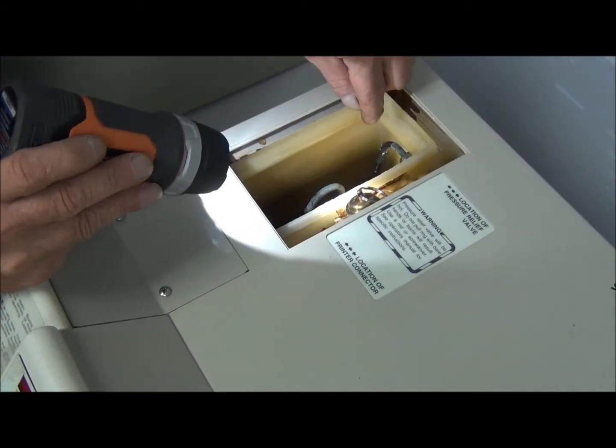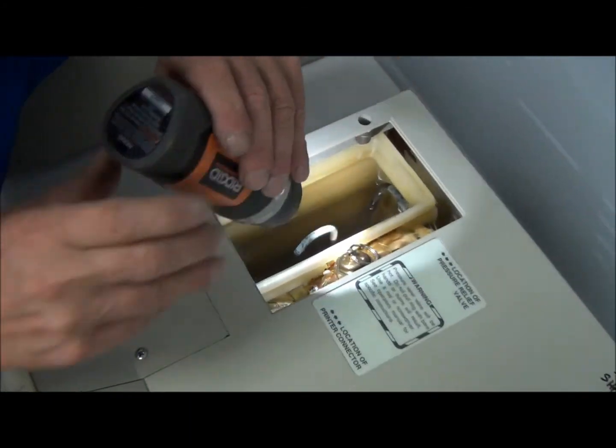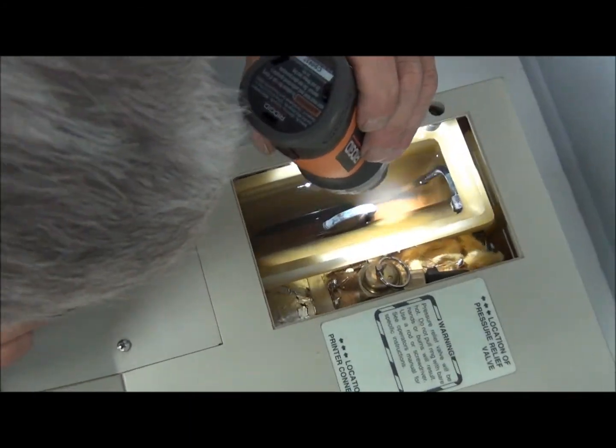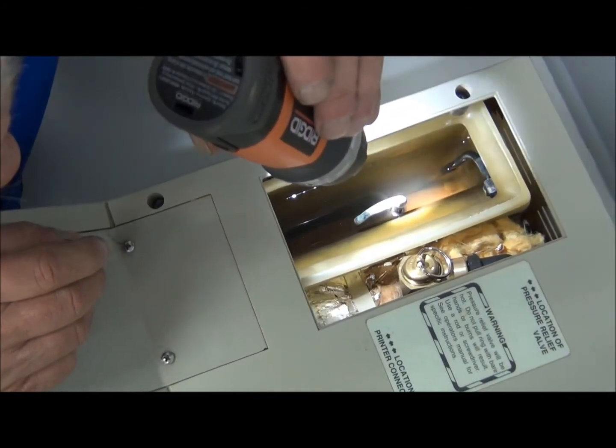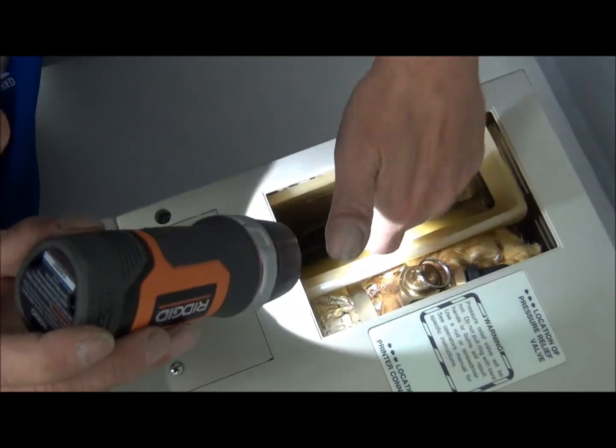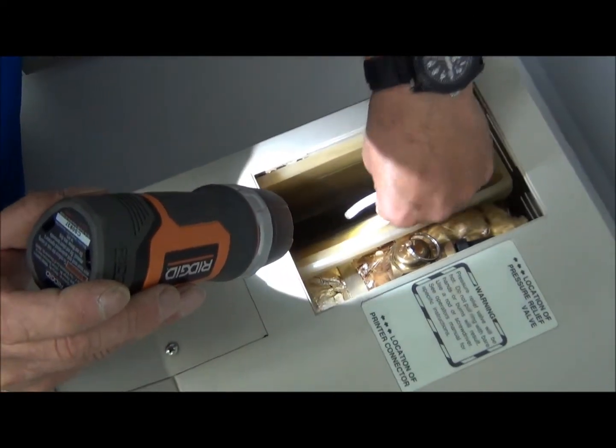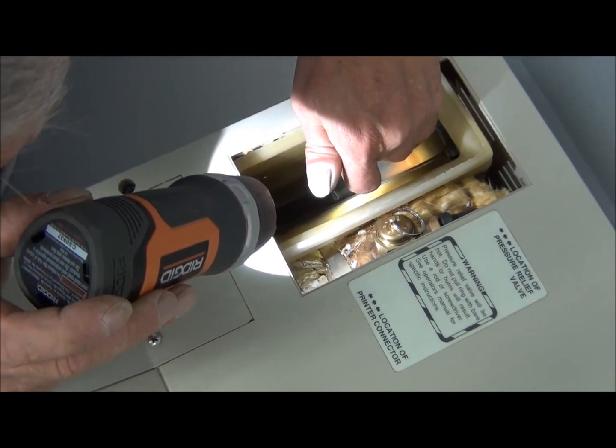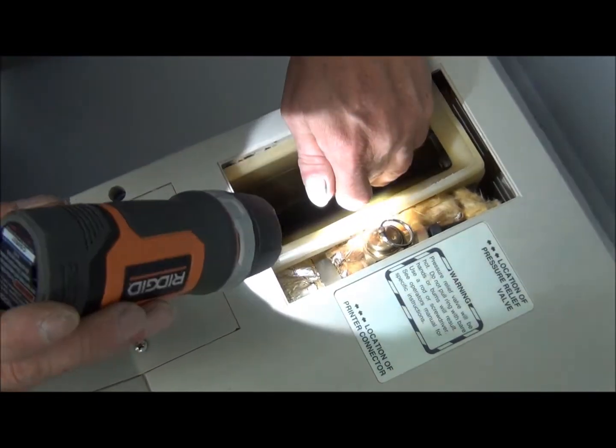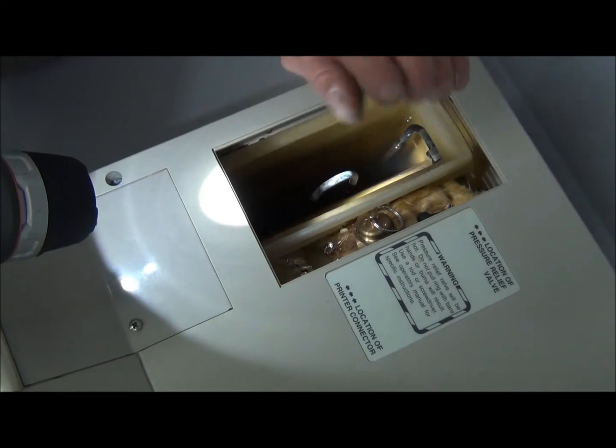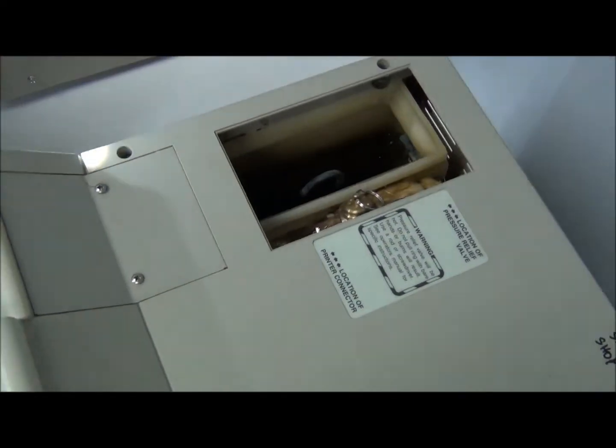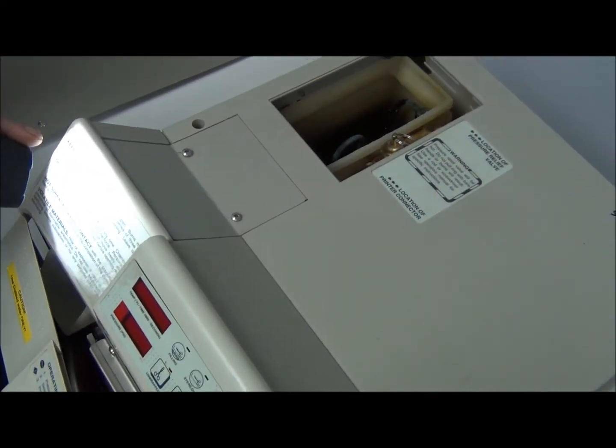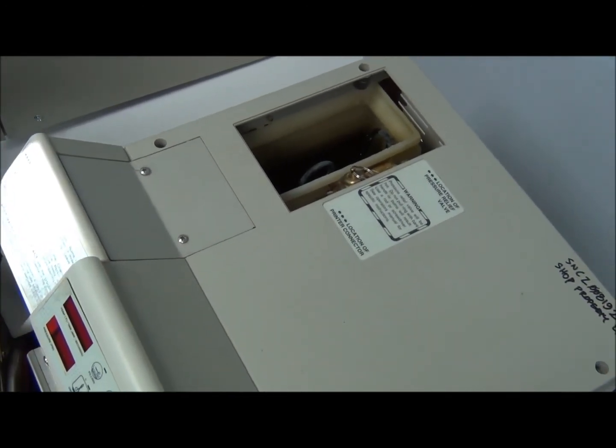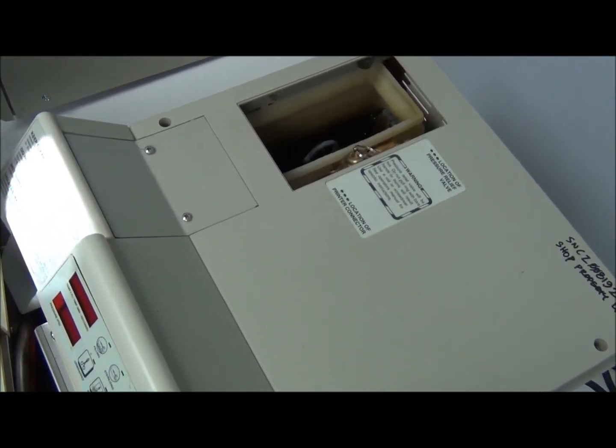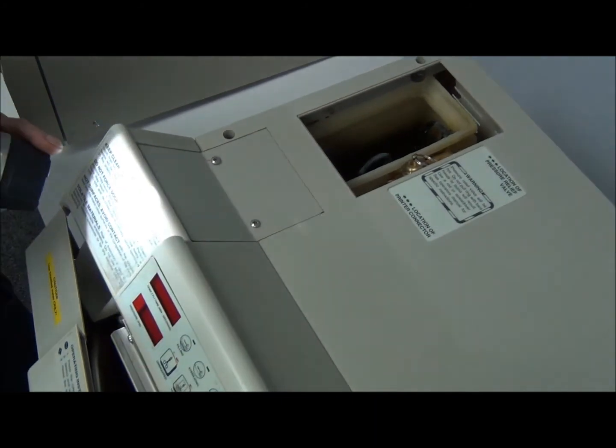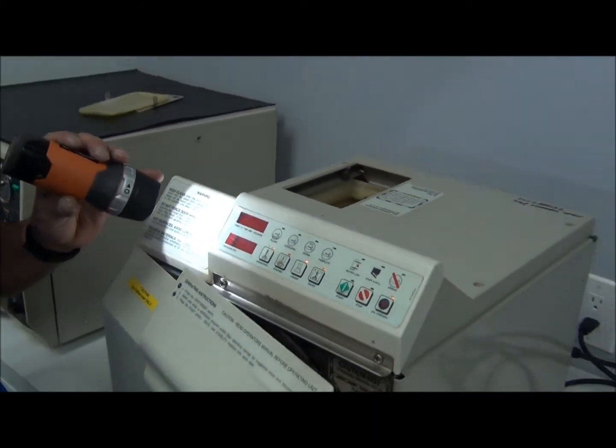Now let's move into the reservoir. We want to make sure the reservoir is very free of gunk and debris, which it is. We want to visually inspect our condenser tube for cracks, corrosion or pits, and everything looks good. Now we're going to leave the lid off, and we're going to run a cycle so we can perform some steam checks and a bellows check or a steam trap check. We will tune back in as soon as the sterilizer is up to temperature.